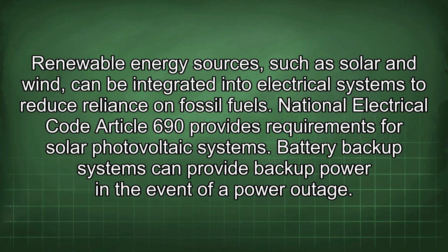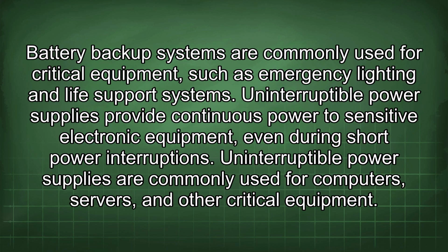National Electrical Code Article 690 provides requirements for solar photovoltaic systems. Battery backup systems can provide backup power in the event of a power outage. Battery backup systems are commonly used for critical equipment, such as emergency lighting and life support systems. Uninterruptible power supplies provide continuous power to sensitive electronic equipment, even during short power interruptions. Uninterruptible power supplies are commonly used for computers, servers, and other critical equipment.